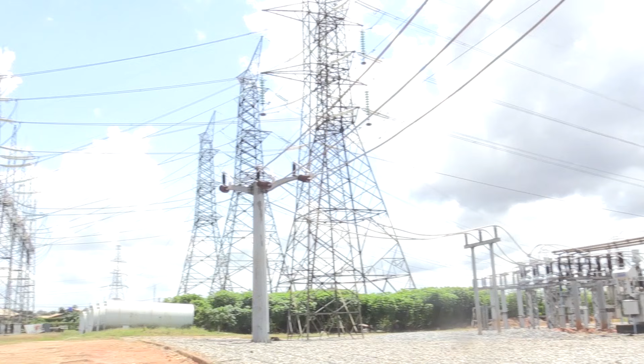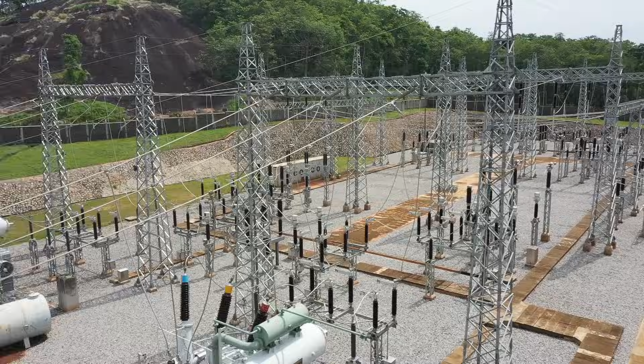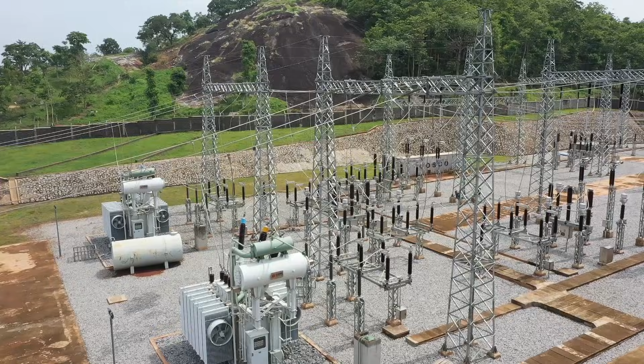What key projects have been executed in this sub-region? So many projects. In the Enugu sub-region, we have the Igwaje 330/132kV substation, where we commissioned a 75 MVAR reactor and also a 75 MVA transformer. That transformer increased the capacity of Igwaje, and we now have excess capacity. We're also going to provide N-1 redundancy, so whenever the existing one has an issue or trips, we can easily switch over customers to the next one.